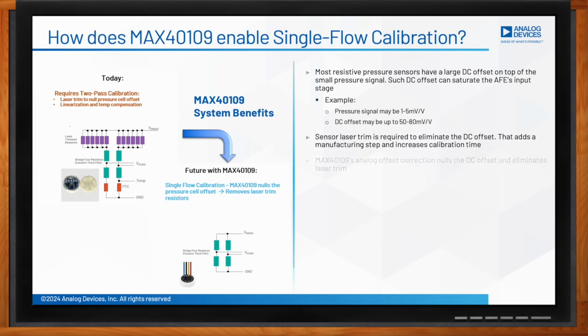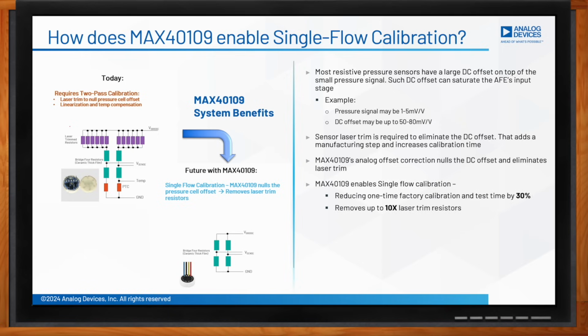The MAX40109 provides an analog offset correction at the IC level, which cancels the pressure cell intrinsic offset. In this way, the first step with laser trim resistors can be eliminated. By doing so, the overall one-time factory calibration and test time can be reduced as much as to 30%. At the same time, up to 10x or more laser trim resistors can be eliminated. The MAX40109 has all the features inside to perform the second step, which is the linearization and temperature compensation. Indeed, the second step becomes the only unique calibration step.